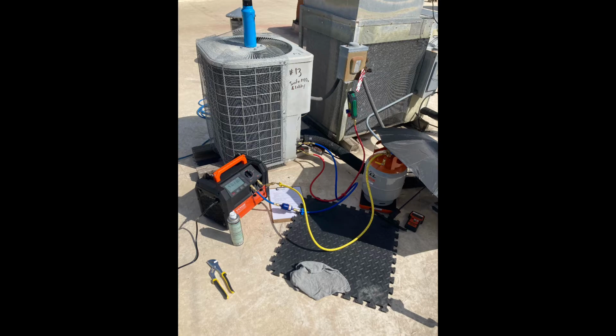Again, it's R22. So I'm going to label the recovery bottle R22. I'll zero out my scale once I have the tank on the scale. Then once I'm done recovering all the refrigerant I can out of the system, I'm going to write with a Sharpie how many pounds of refrigerant I recovered on the tank.